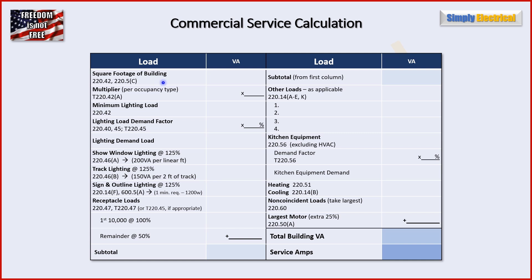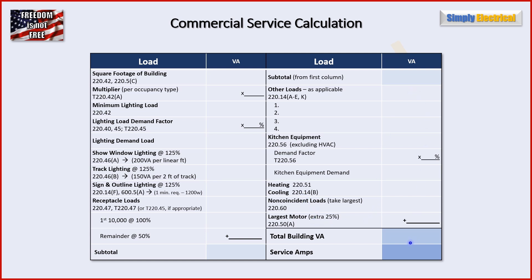You're going to start with the square footage of your building, then find your multiplier from Table 220.42A. That gives you your minimum lighting load. Then you apply demand factor to get your lighting demand load. Then you jump into specialty lighting — show window, track, and sign and outline lighting. Then receptacle loads. We add all these together and get a subtotal, then move on to other loads, defined in 220.14A through E and K. Then we get into kitchen equipment, which is treated specially — especially important for a restaurant. Then heating and cooling, non-coincident loads, and the largest motor. Once we tally all these up, we have our total building VA and can divide by voltage to get service amps.